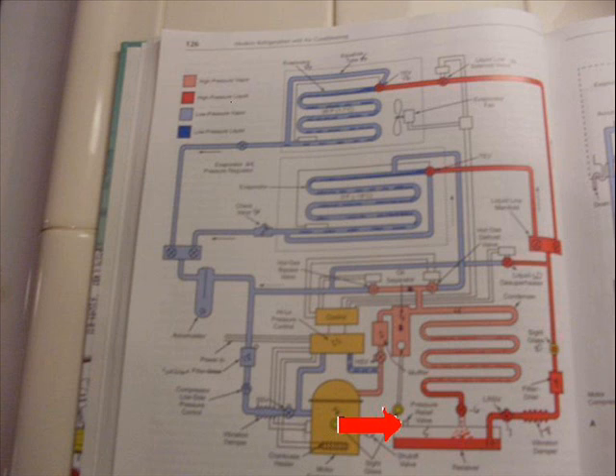The last type of pressure relief valve is the same type you have on your water heater at home. It's a spring-operated ball-type check valve that when the pressure exceeds the spring range, the valve spits out pressure. But as soon as the pressure is relieved, it resets itself. So you have a spring-resettable pressure relief valve. Spring-resettable, carbon disc, and solder.